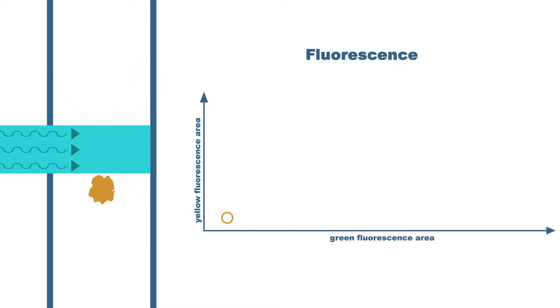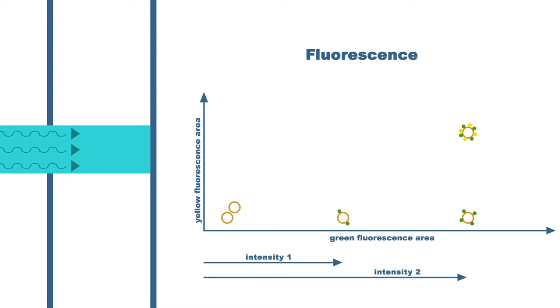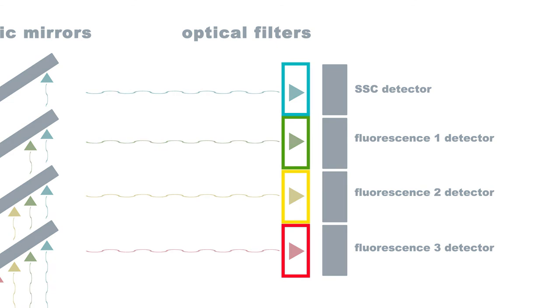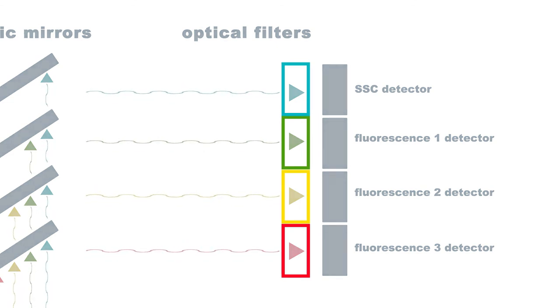By staining events with various fluorescent dyes, quantification of fluorescence intensity is realized according to light intensity correlating to the number of fluorophores on the events. The more fluorophore molecules are attached, the higher the detector signal is. Because detectors are linear over a wide dynamic range, intensity of incoming light can be quantified. A double amount of fluorophore attached to an event leads to a double intensity of fluorescent light and a double intense signal at the correlated detector output. Band pass filters in front of the detectors only allow transmission of selected wavelengths. The emission intensities of fluorescent dyes can be thus selectively assigned.